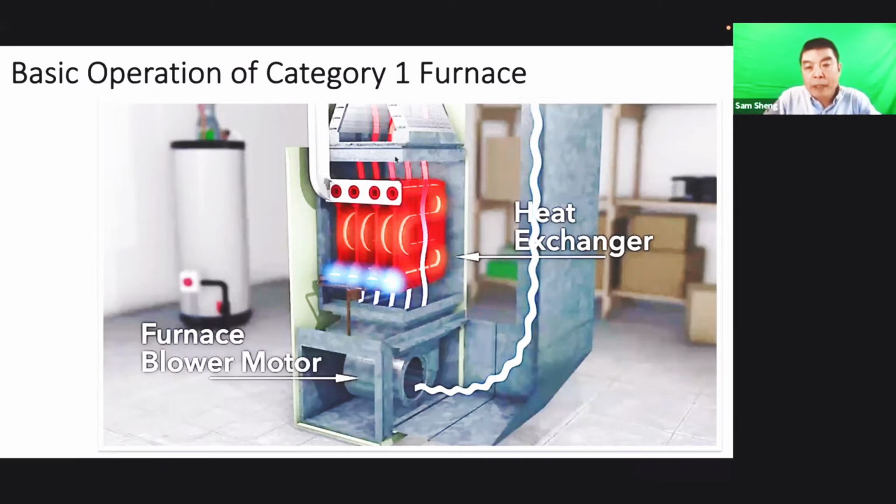Yeah. Sometimes we cannot see the crack from the top. But we can use a carbon monoxide detector. So when carbon monoxide is detected, normally this means a heat exchanger problem. Yes, so this is very important. Nobody repairs the heat exchanger. If it is a heat exchanger problem, normally we should change to a new furnace.